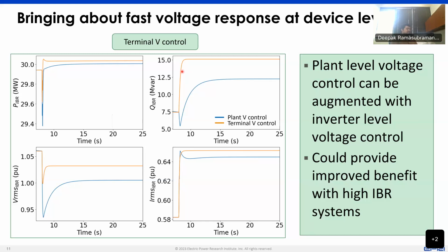The other thing is that the characteristics and response a synchronous machine provides are a lot of times governed by its natural characteristics, its mechanical properties, the way it is designed, constructed and built. If you can take those physical and mechanical characteristics and write a mathematical equation for them, you can put that equation into the control of an inverter. When you do that, you are no longer bound by the physical constraints of the machine that may have restricted the range of a certain parameter in that equation. So now, in control, you can potentially have an infinite range of that parameter's value, which is both a good thing and a bad thing.